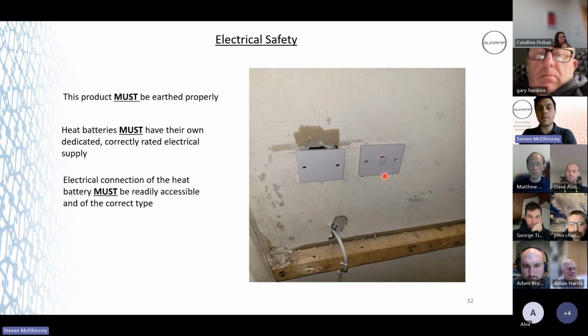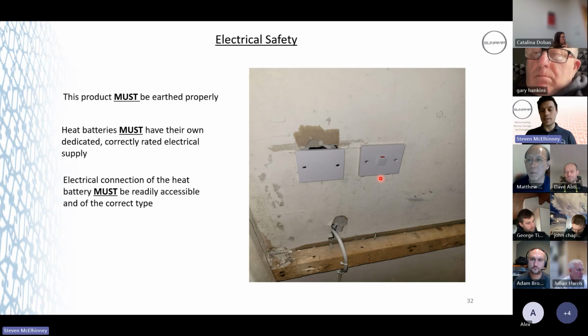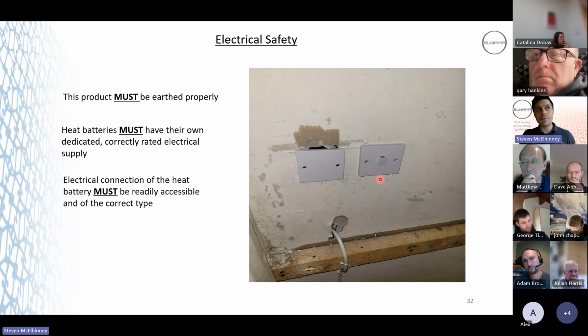So for the Thermino E and the ePV, your Thermino E, that's just a 20 amp appliance switch double pole isolator. That's what you require, because remember it's a 16 amp minimum rated switch that we need. So if you search 16 amp double pole isolators, it starts coming up with rotary isolation switches and stuff. Your customer's never going to have that in their kitchen, are they? They've just had their kitchen installed and you've got a big rotary isolator on the wall. Not going to happen. So you go to the next level up, and it's a 20 amp appliance switch.